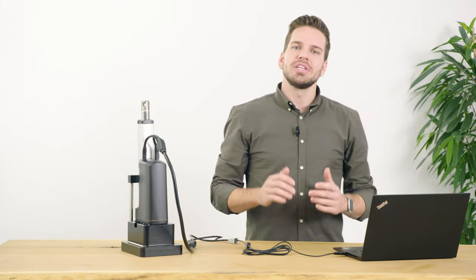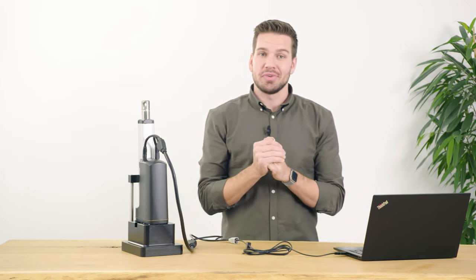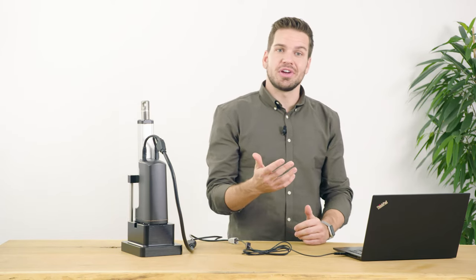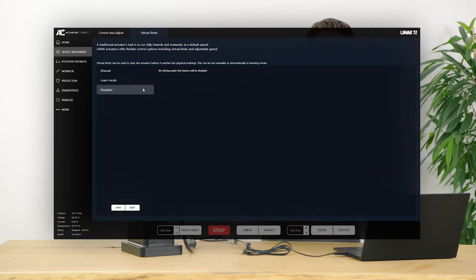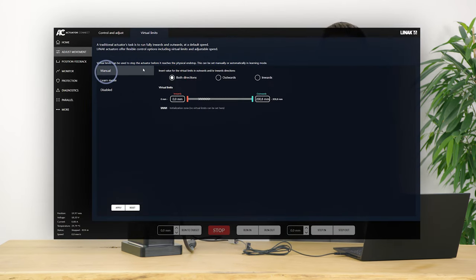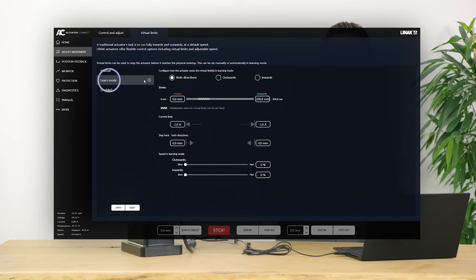Virtual limits can be used to stop the actuator before it reaches the physical end stop in both directions. This can either be preset from the factory or configured in Actuator Connect. This is particularly useful if you're trying to use the actuator for prototyping or have multiple actuators in stock that you'd like to adapt to various fits in the application. It can also be convenient for applications where the stroke length occasionally needs to be adjusted. These virtual limits can be set manually if the stroke limitation is known in advance or automatically using learn mode.